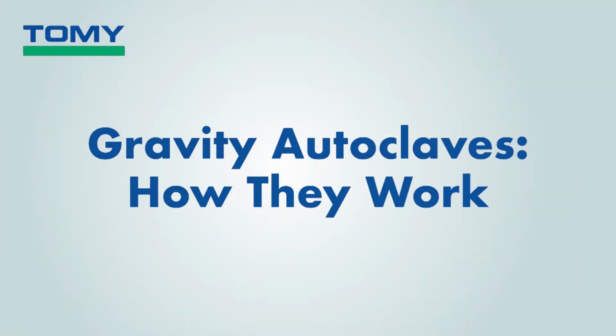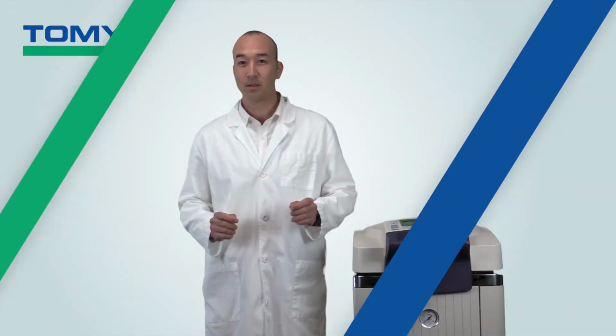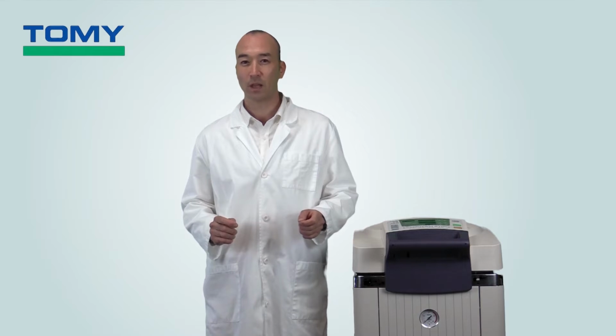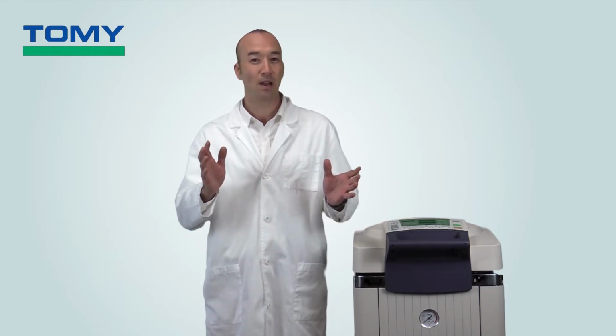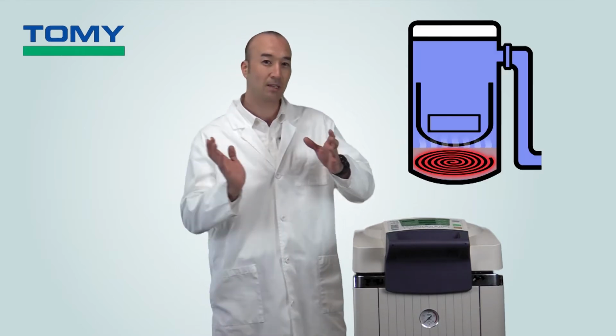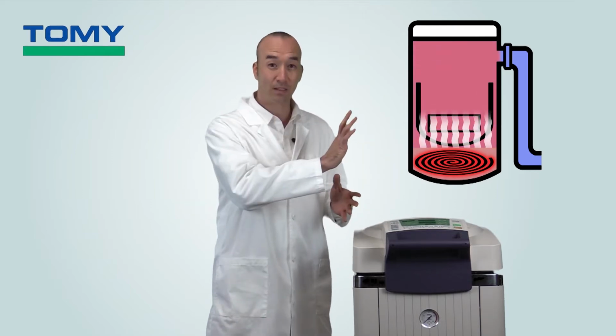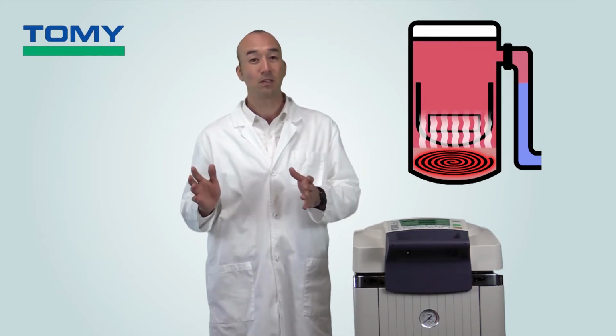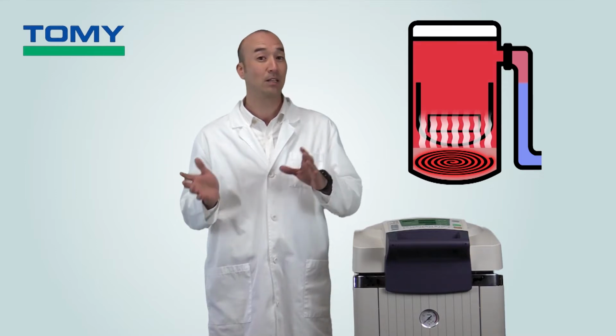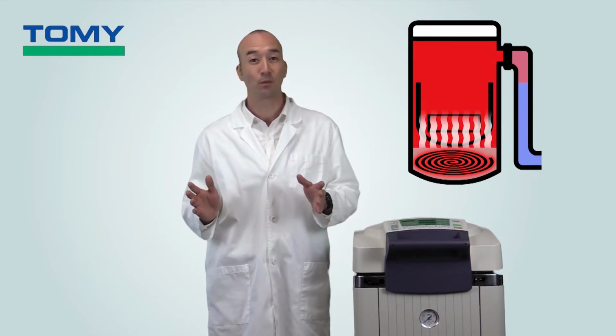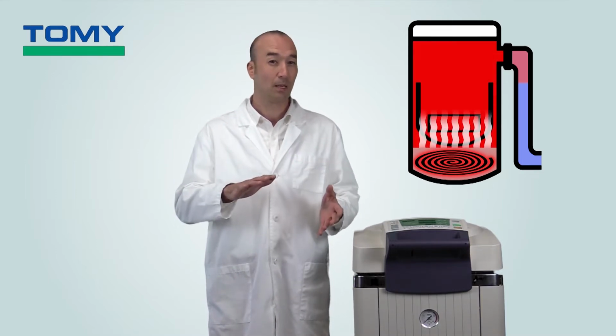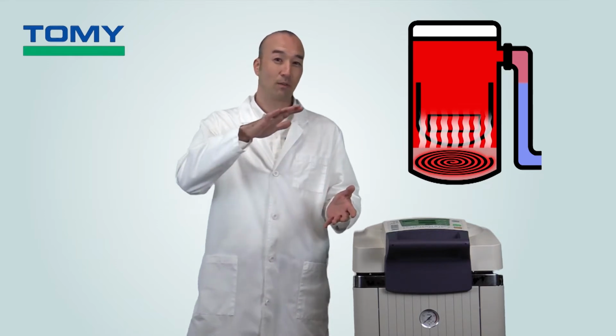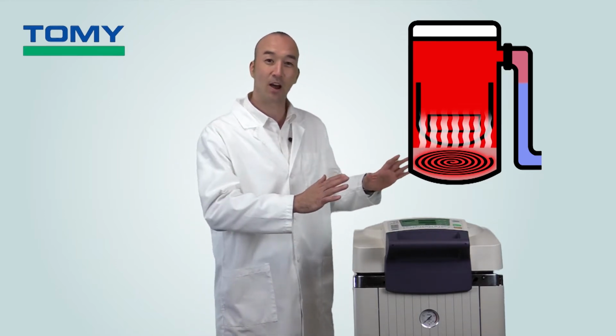The first of the two main types of steam sterilization is gravity autoclaving, also known as gravity displacement autoclaving. This is the most basic form of autoclave and involves creating steam inside the autoclave chamber, which displaces ambient air and forces it out of the exhaust valves. This replacement of the air in the chamber gives it the name gravity displacement and is also sometimes referred to as downward replacement because the relatively cooler ambient air travels downward and is forced out of the autoclave.